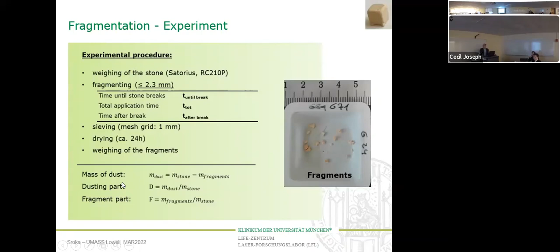Then we can clearly see that the time until break changes. And we take this time because once the stone is breaking, then the chasing starts. We need to chase two different compartments for this. And in this regard, if we have short pulses, it takes much longer to get these two parts really destructed than in the case of longer times. Yeah? And also the destruction during this time is much higher.